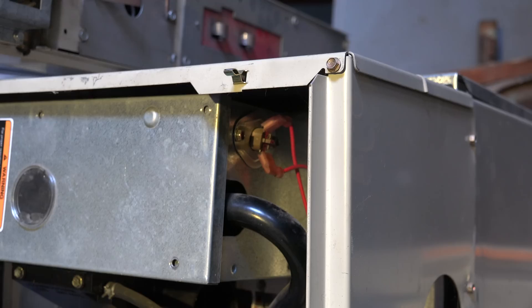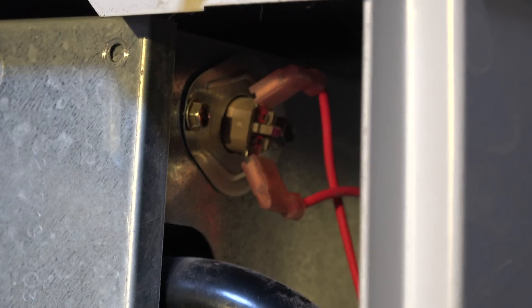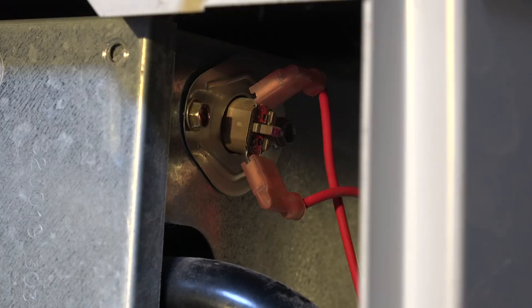Now here is a third example of a rollout switch. You can see the button in the center of it. Interesting thing about this one: this one's not a factory replacement rollout switch. That is an aftermarket switch that was placed in there. It's the incorrect switch for this furnace.